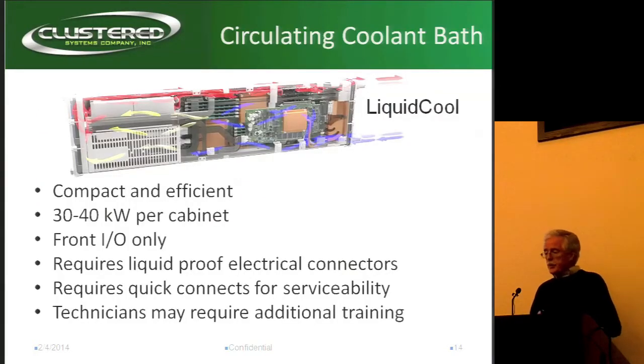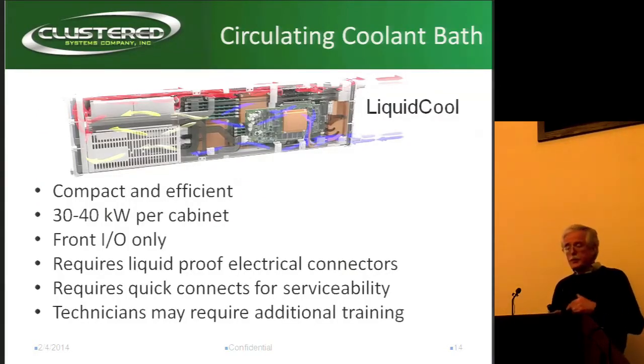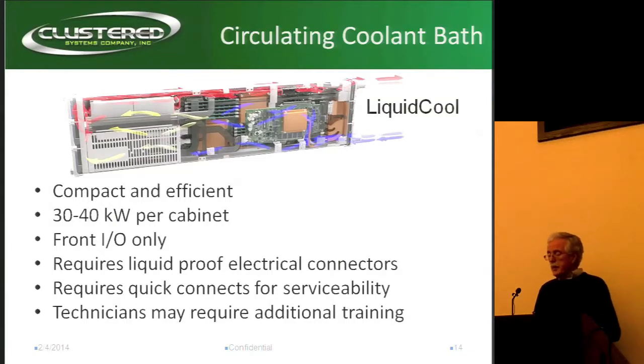The first one is LiquidCool. What they do is pass liquid through a single heat exchanger — it's very compact and pretty efficient, so they can probably pack these in tightly. The issue is that you can only reach one end for putting I/O on it, and you need to ensure liquid-proof electrical connectors because the whole thing is flooded with liquid.